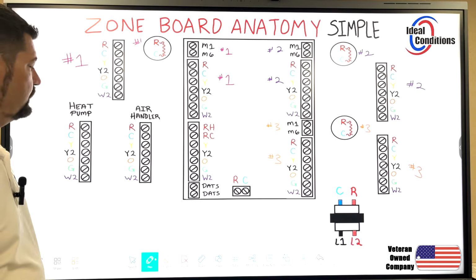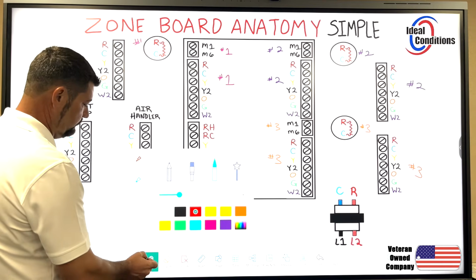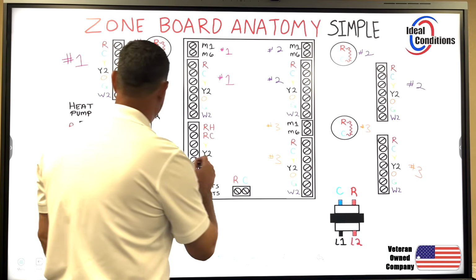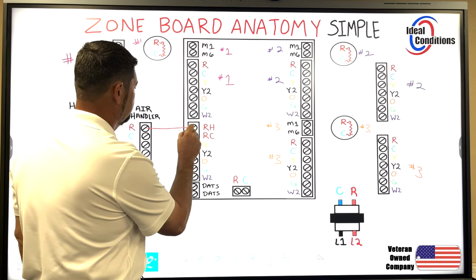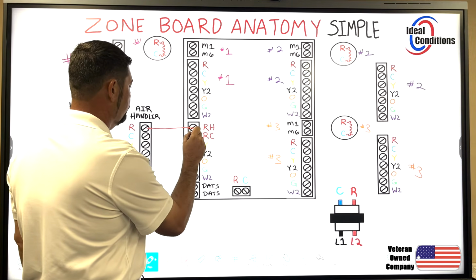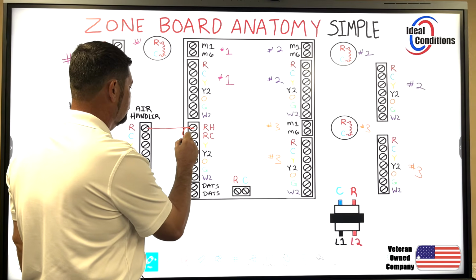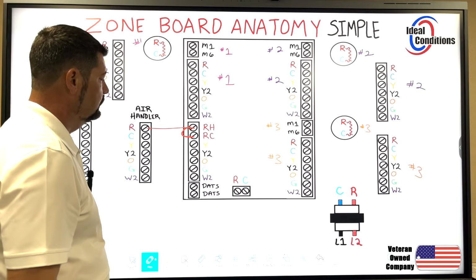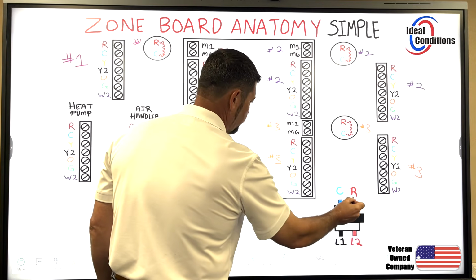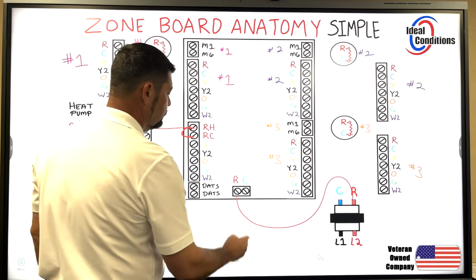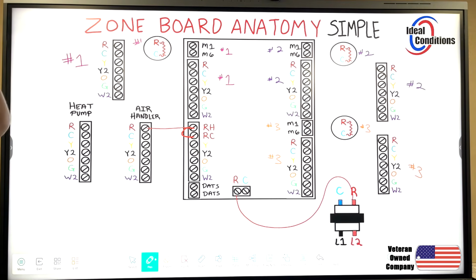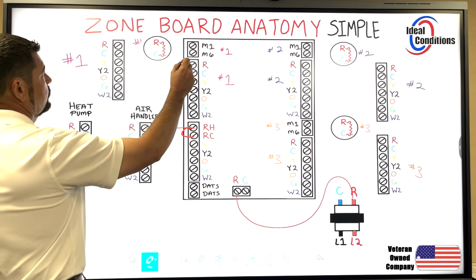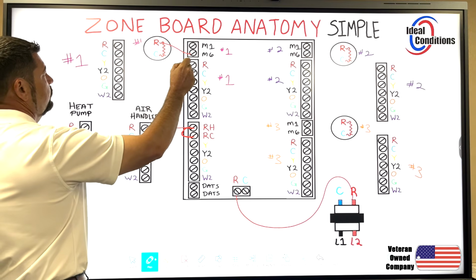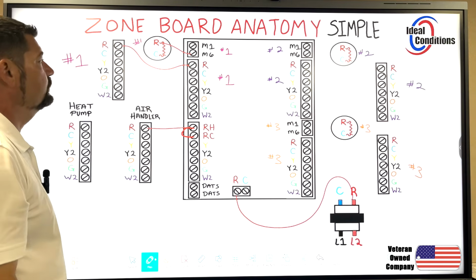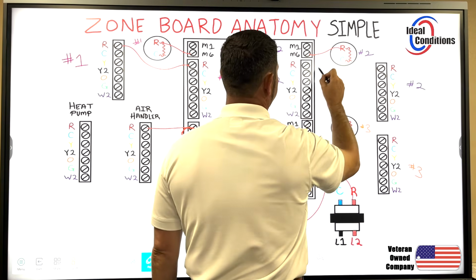And we're just going to connect all the dots. It's going to be very easy. We're first going to run the air handler into RC/RH. There will be a jumper there between RC and RH. Okay, we're going to go ahead and take 24 volts off our secondary transformer and wire that into our zone board. All right, we're going to take our M6 up to our dampers, and we're going to take R and start coming over to our thermostats and landing them, and we're just going to repeat that process.